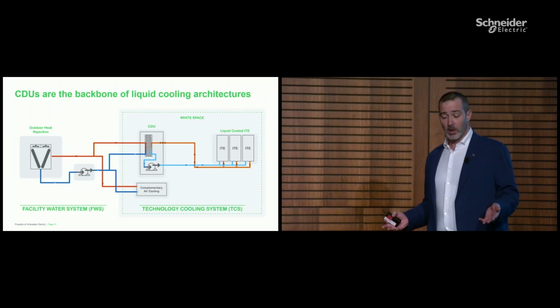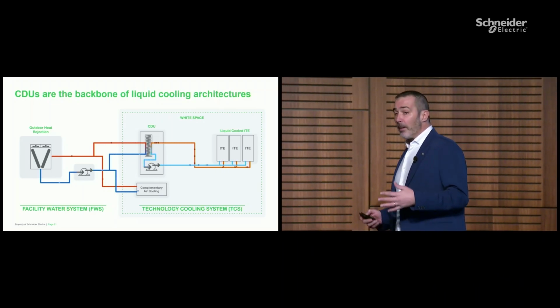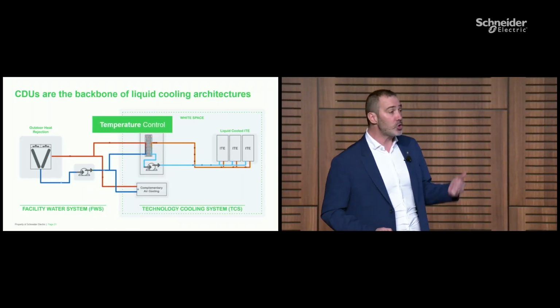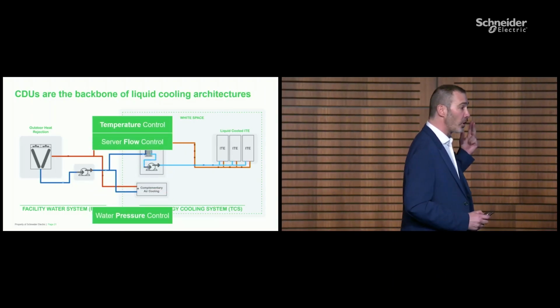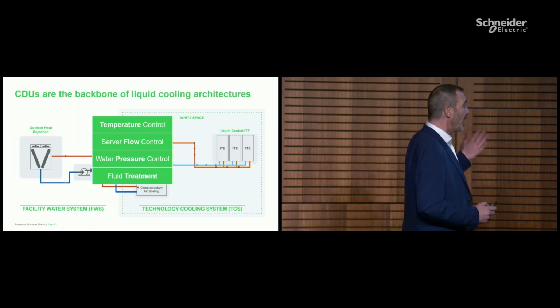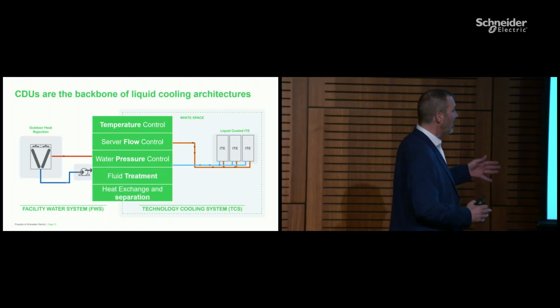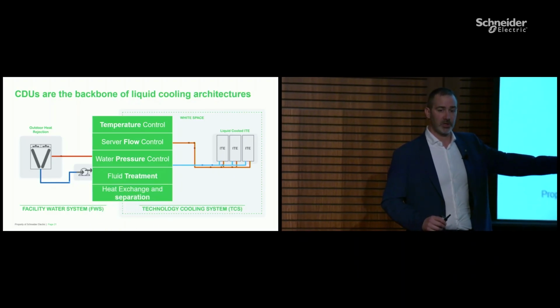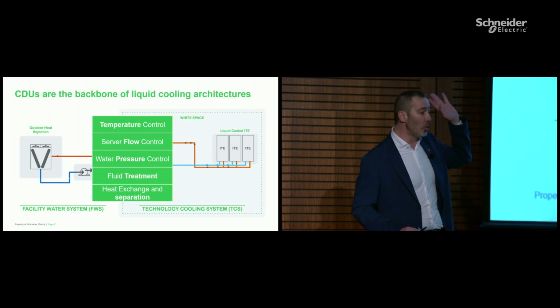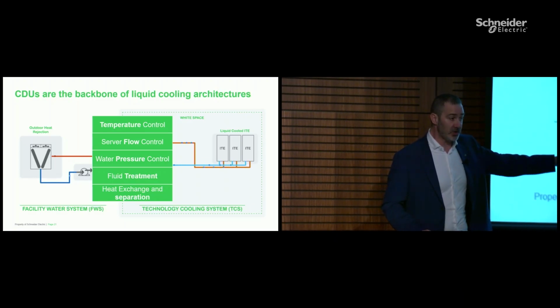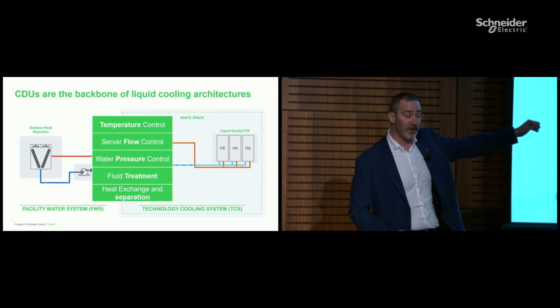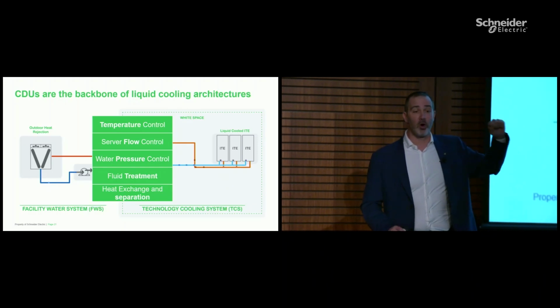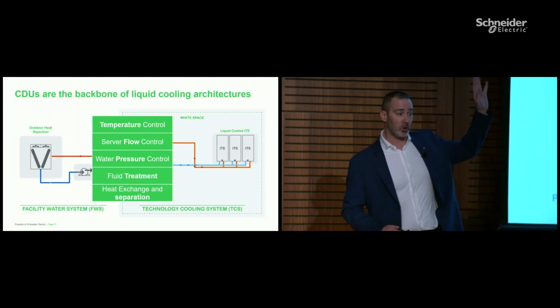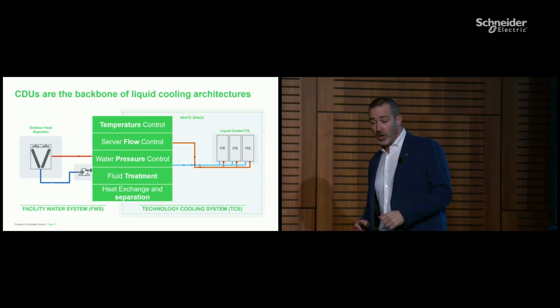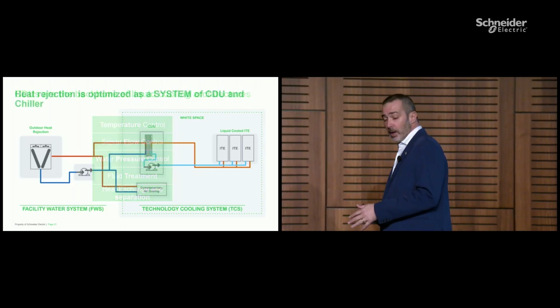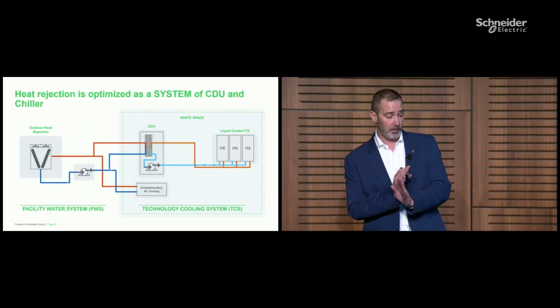Why do we need to separate? Because we need to keep under control the temperature, the pressure, the quality, the filtering, and the treatment of the water on the TCS. The TCS needs to use glycol, stainless steel material, control of filtration, control of the water, control of the pressure, control of the temperature. So the CDU is this backbone.